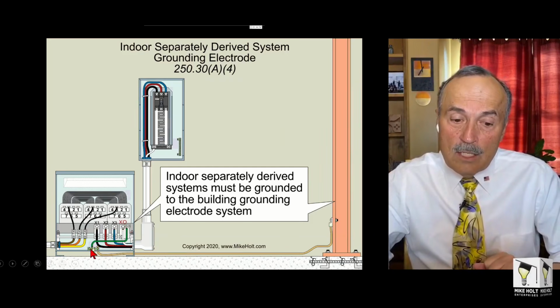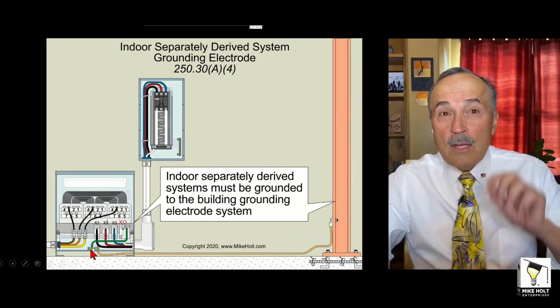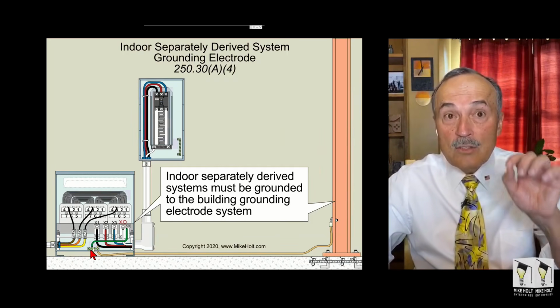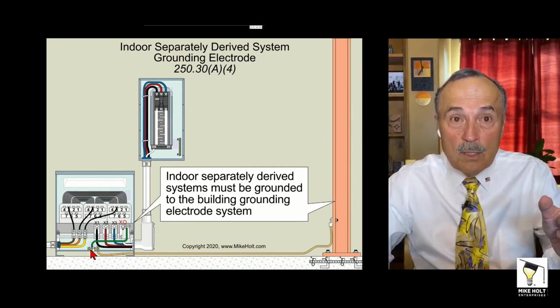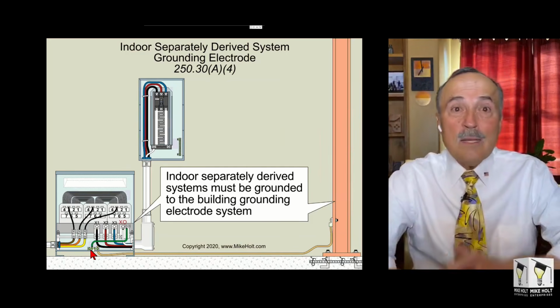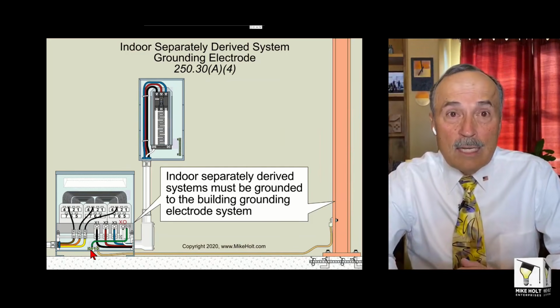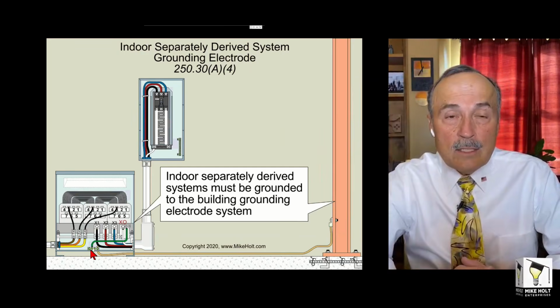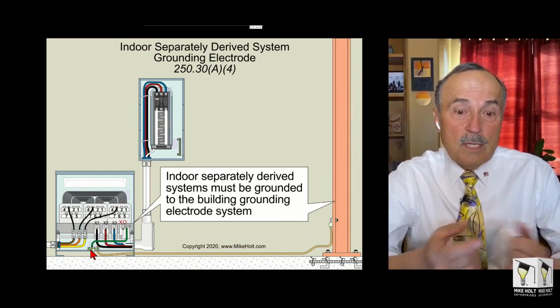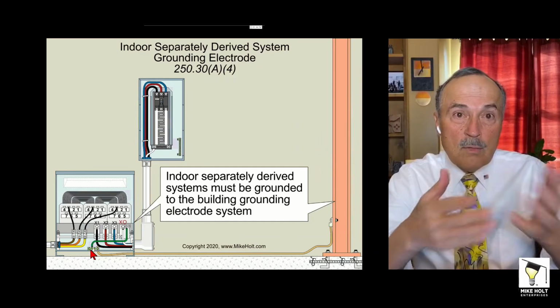No, because if the XO is connected, let's say, to the grounding bar, 450.10(A) says you have to have a grounding bar in the transformer. Well, if you're going to go XO to the grounding bar, why the heck would you run the grounding electrode conductor all the way up to the XO when you've got a grounding bar there and it's required to be there? But you could if you want to. It doesn't really matter. Either way is fine.